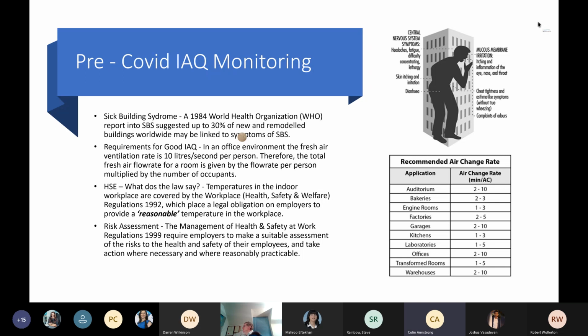In an office environment, the fresh air ventilation rate is 10 litres a second per person. Therefore, the total fresh air flow rate for rooms is given by the flow rate per person multiplied by the number of occupants. I think it's quite an important thing that the flow rates need to be right in a room, and I'll come on to that in a short while, to ensure that you've got that good quality of air there.